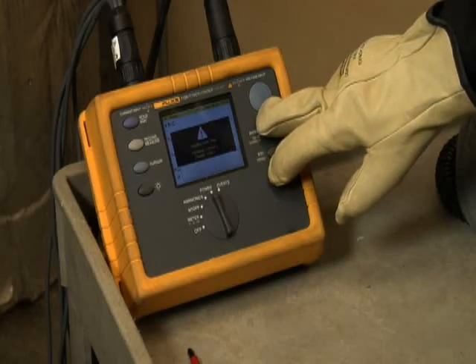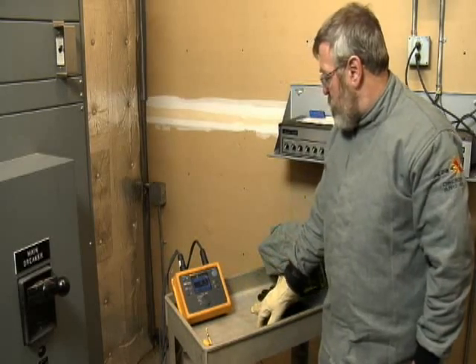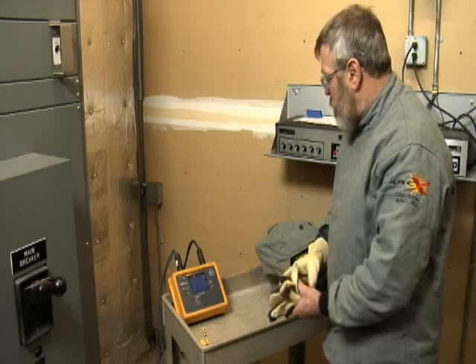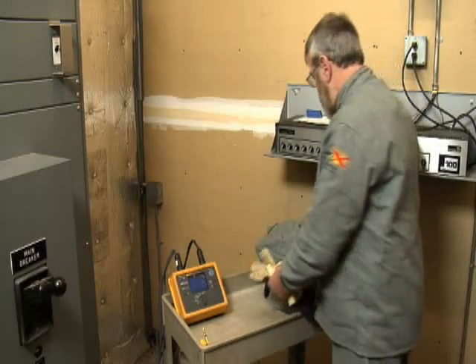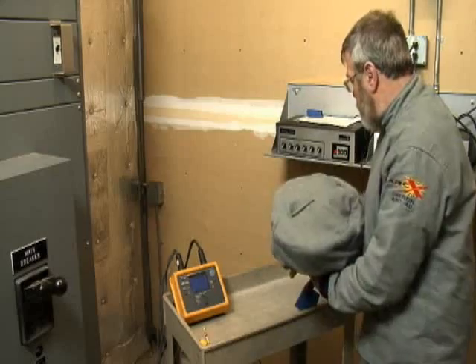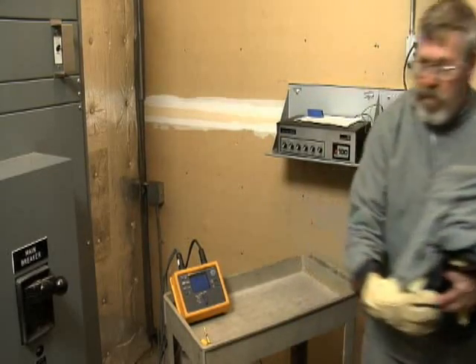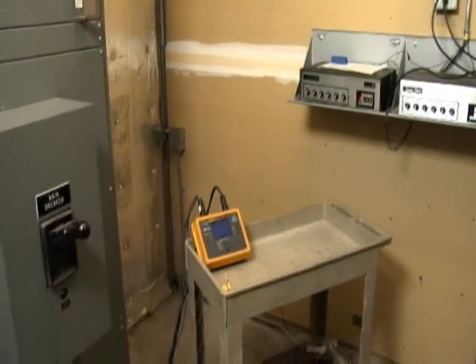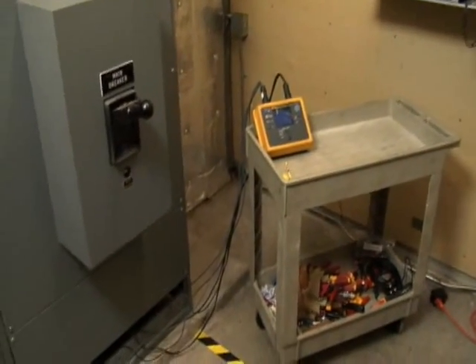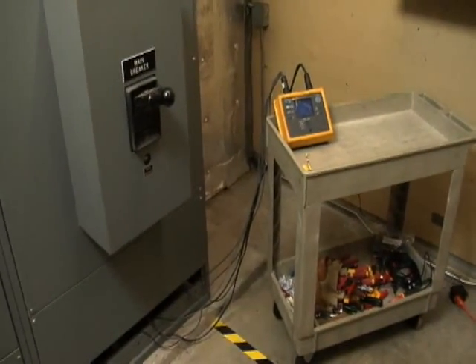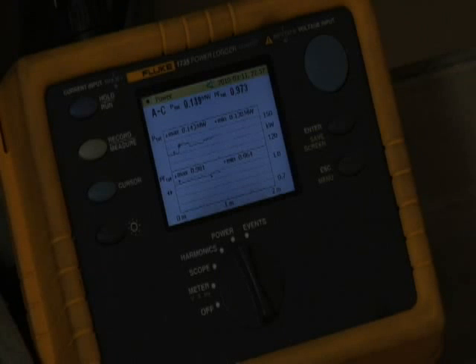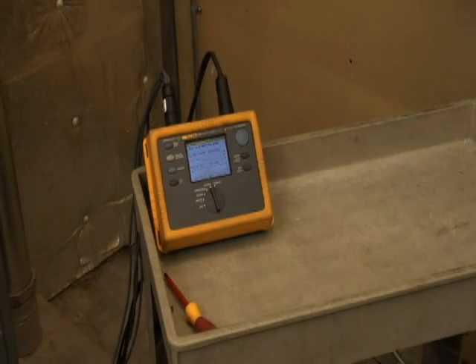It's managing these values that will save you money. Start recording and walk away. You want to capture the full demand cycle if at all possible. In particular, we want to use less energy at times when it's the most expensive. But we also want to see how much we're drawing during the middle of the night to see if there are things we could shut off, and see what our power draw looks like when multiple loads are working simultaneously. Later on, we'll use this data to see if we can change our operation to use less energy.